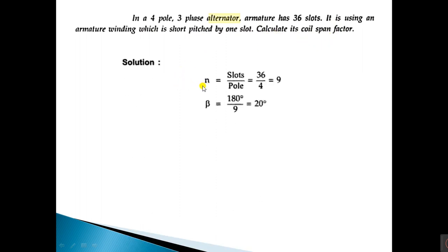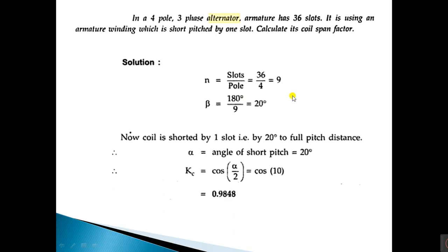Let us see an example based on coil span factor. In a four-pole three-phase alternator, the armature has 36 slots, using an armature winding which is short pitched by one slot. Calculate its coil span factor. First, calculate n — the number of slots per pole: 36 divided by 4 equals 9. Then calculate beta: 180 degrees divided by n, so 180 divided by 9 equals 20 degrees.